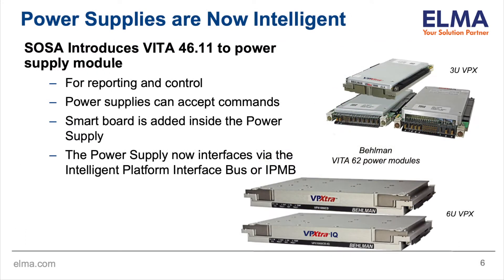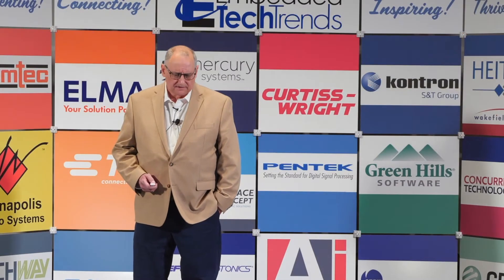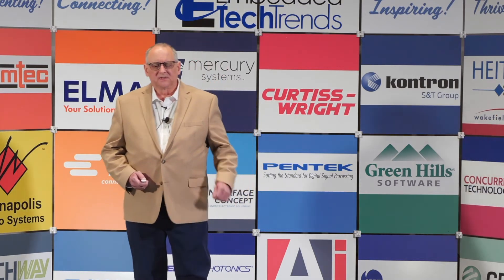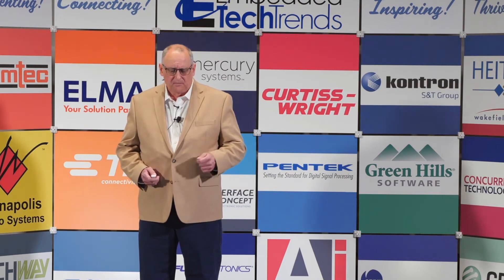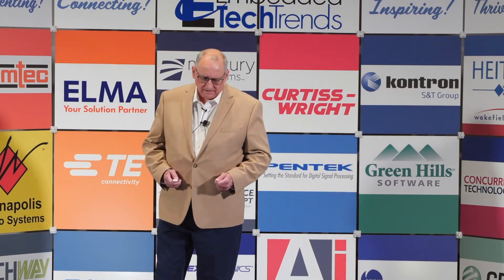Looking at things we can interface to: as mentioned yesterday, we now have intelligent power supplies. This intelligence has been worked on for some time and discussed in the SOSA working groups. This capability introduces VITA 46.11 to the power supply module, so the power supply can now report and be controlled. Power supplies can accept commands, and this is being implemented by adding a smart module inside the power supply to enable it to interface via the Intelligent Platform Management Bus, or IPMB.